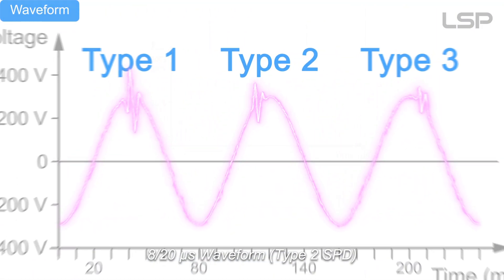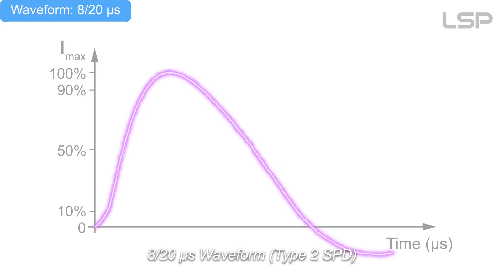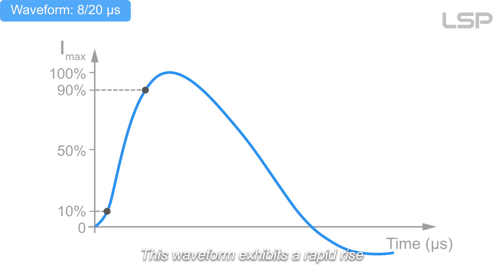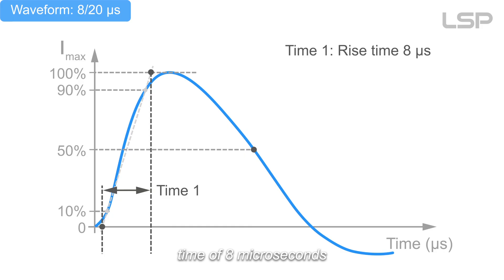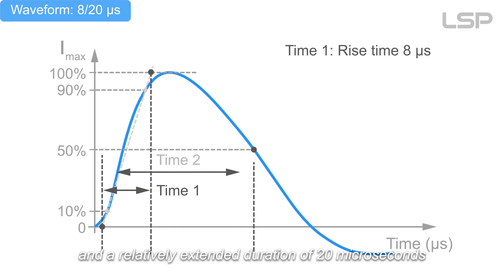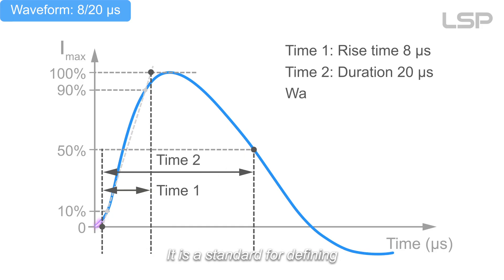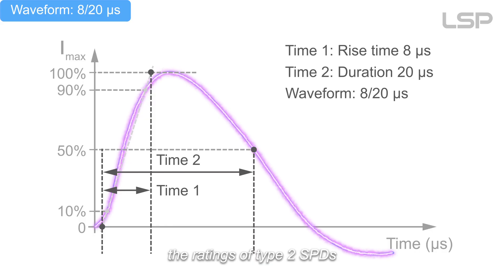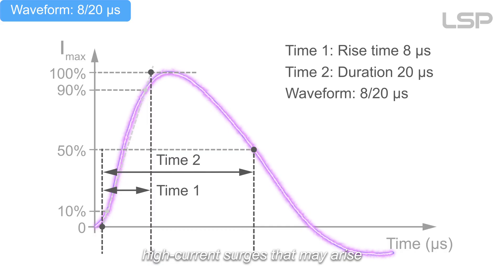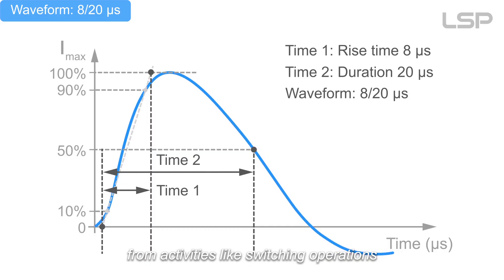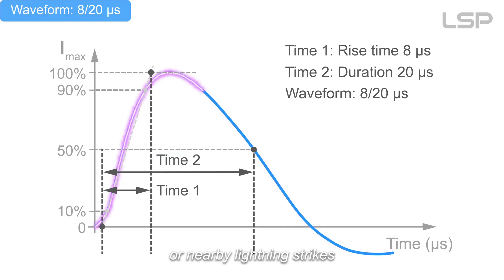The 8/20 microsecond waveform is the standard for Type 2 SPDs. This waveform exhibits a rapid rise time of 8 microseconds and a relatively extended duration of 20 microseconds, and is a standard for defining the ratings of Type 2 SPDs. These devices are engineered to protect against fast-rising, high-current surges that may arise from activities like switching operations or nearby lightning strikes.